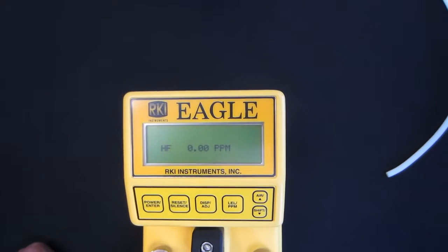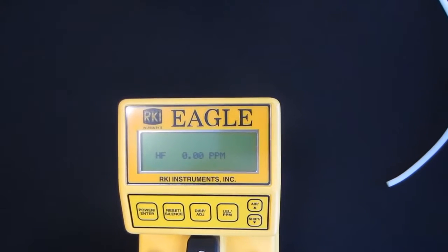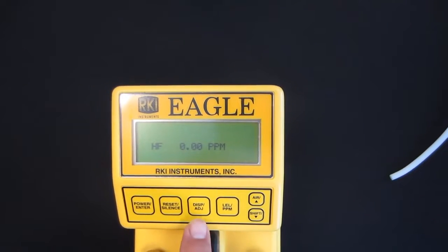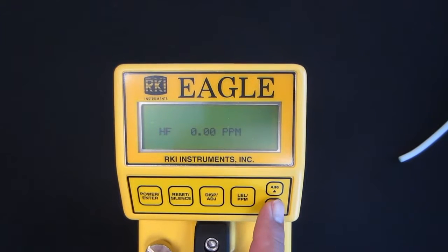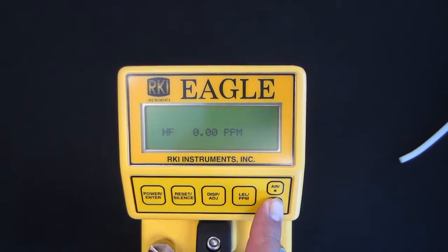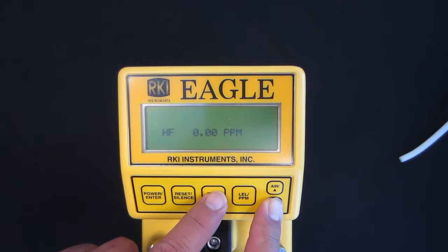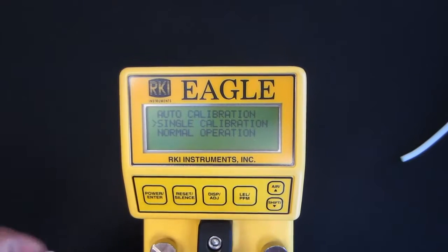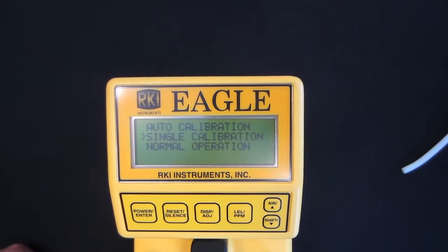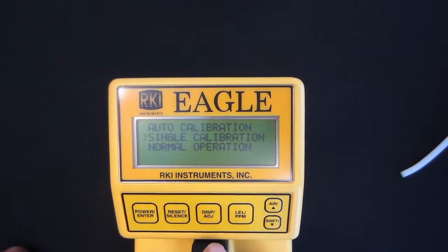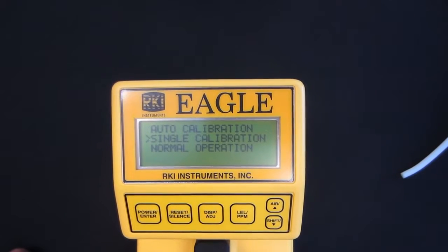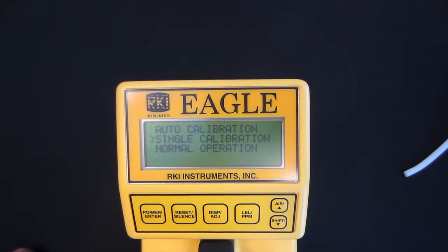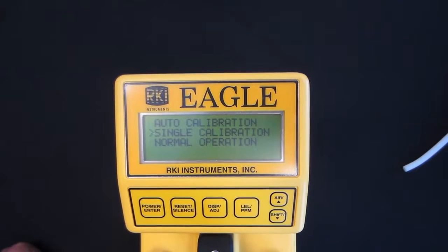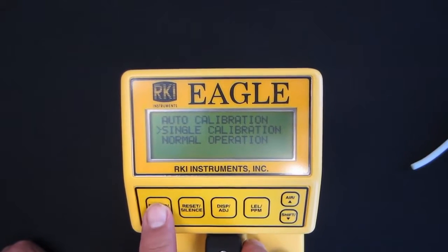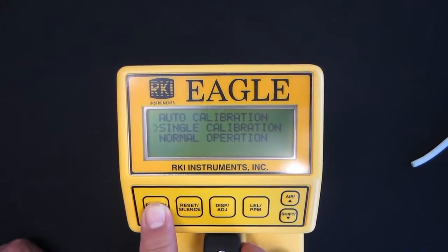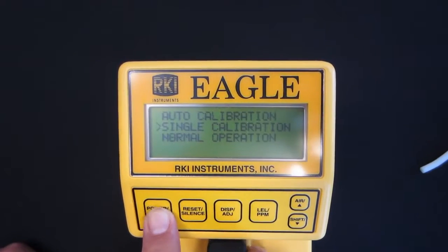Okay. Next, we're going to put the Eagle into the calibration mode. We're going to press and hold down the Shift Down button, and then the Display button, and that brings up the calibration menu. Right now, it's flashing on single calibration, which in fact is what we need to do. We only have one sensor in here, and that is an HF sensor. So we're going to press the power enter button to enter the single calibration mode.